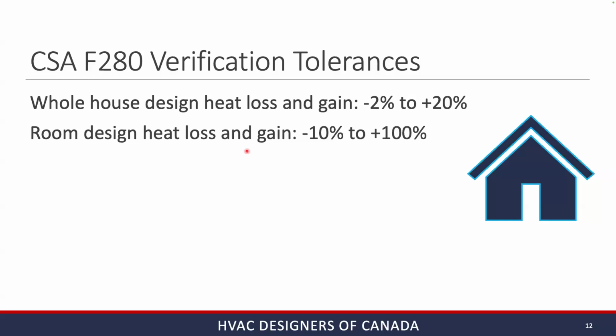On the room side, we decided there's lots more room for tolerance there. If nothing else, I've got a bit more control of distribution with dampers and such like. So they decided, again for the same reason, -10 is probably okay. If the room gets a bit chilly, you'll pick up some heat from other rooms, and you can always throttle down the other rooms. We don't mind going up to 100% above the theoretical correct number, because once again, I can always damper the ducts down or throttle back my hydronic system, or if it's electric baseboard, the thermostat will just cycle.